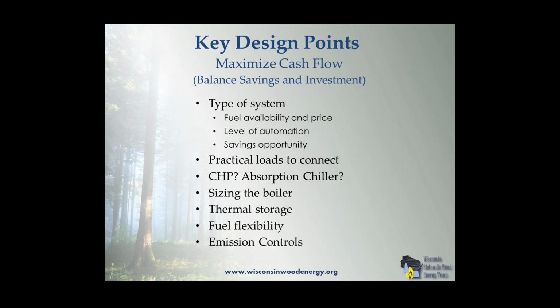It's also very critical to minimizing emissions, because you can tune this boiler so that it ramps up a little bit slower, allowing the thermal storage to take over. You spend a lot less time varying firing rates of that boiler. And as you change firing rates, or go from low firing to higher firing, there's a lot of emissions that take place. Also in the idle mode, there's a lot of emissions that take place. And what thermal storage does, it really helps both the overall efficiency of the system, responsiveness of the system, and greatly reduces emissions of the system during those times of changing loads.